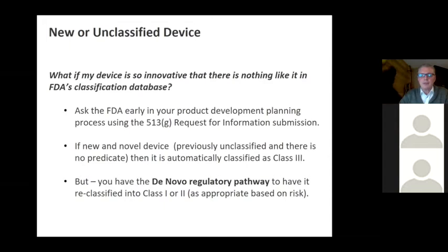That will allow you to get feedback from the FDA on what your device should be classified as from their perspective. But what you're encouraged to do is provide your understanding of what the classification would be and the justification for that, and then ask the FDA if they concur. It is not a good idea just to send your information to them and say, what classification is this? They will come back and say it's class 3.